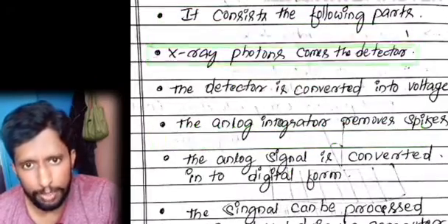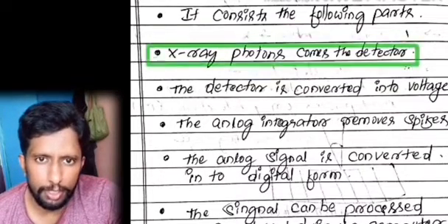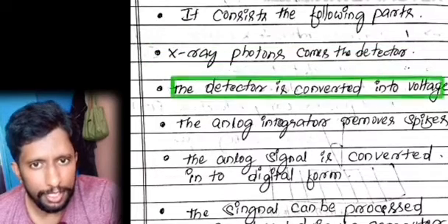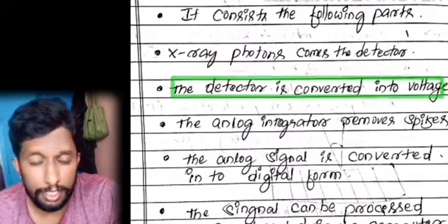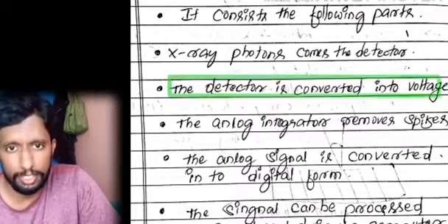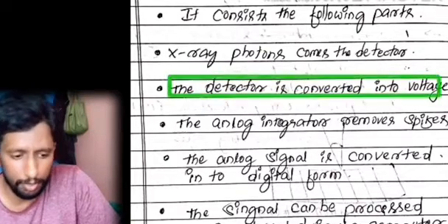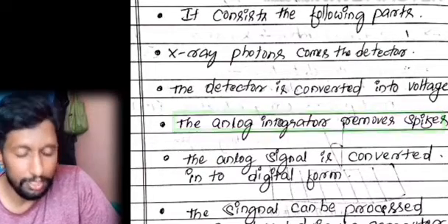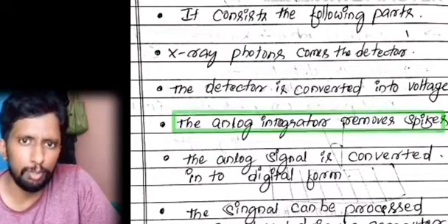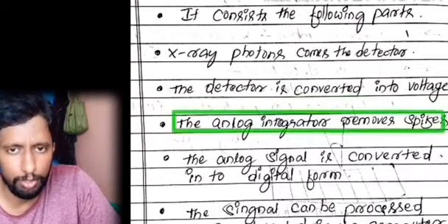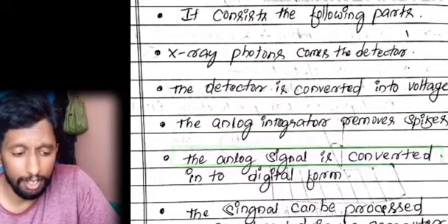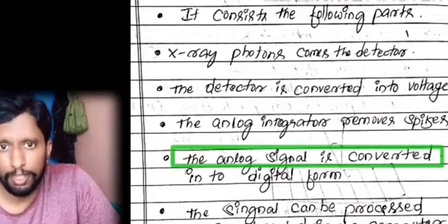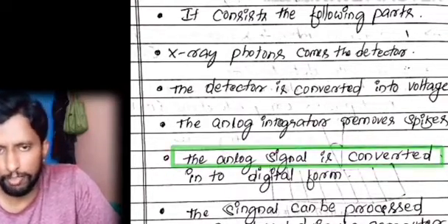In the data acquisition process, X-ray photons come to the detector. The detector converts them to voltage. The analog integrators remove spikes, and then the analog signal is converted into digital form.